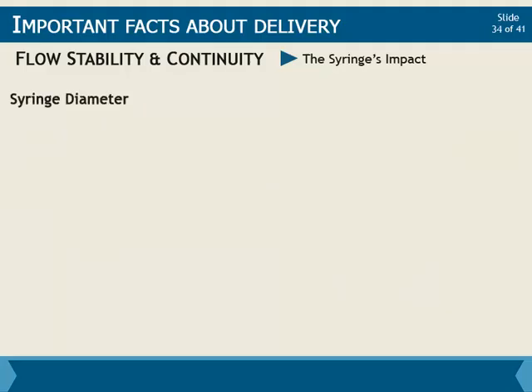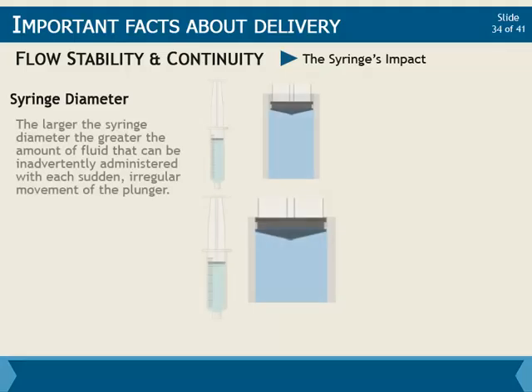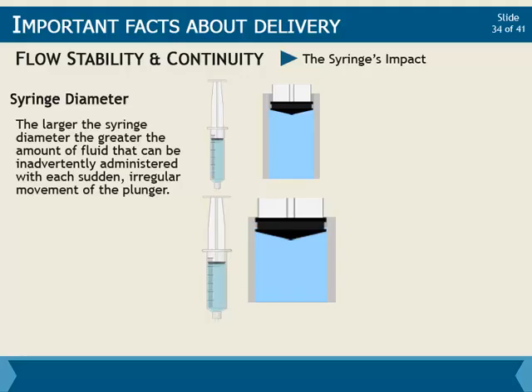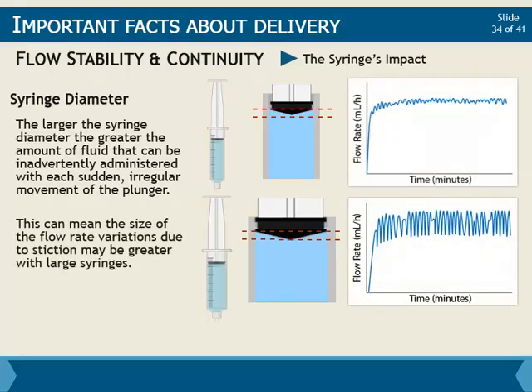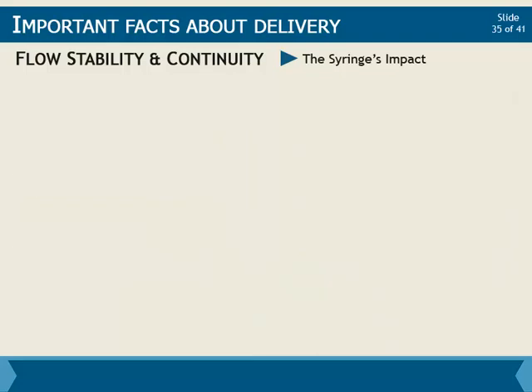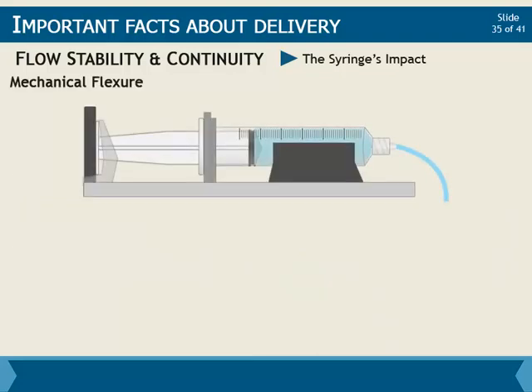Syringe diameter has a role to play here as well with regards to stiction. The larger the syringe diameter, the greater the amount of fluid that can be inadvertently administered with each sudden irregular movement of the plunger. This can mean the size of the flow rate variations due to stiction may be greater with large syringes. Mechanical flexure is something else that can contribute to stiction.